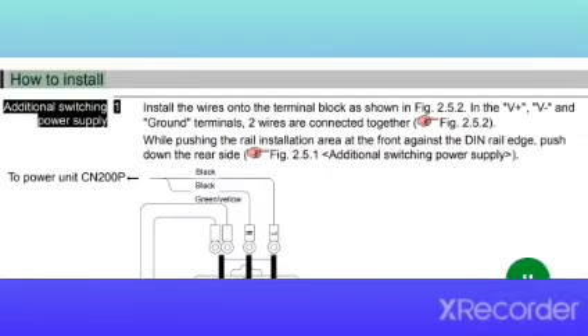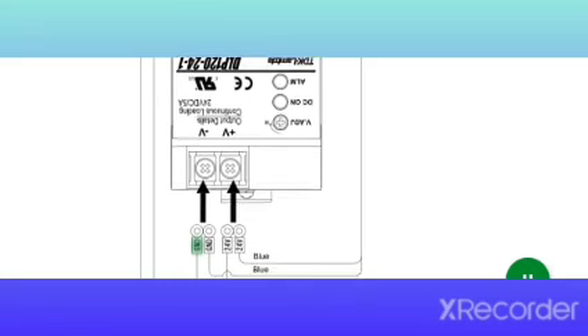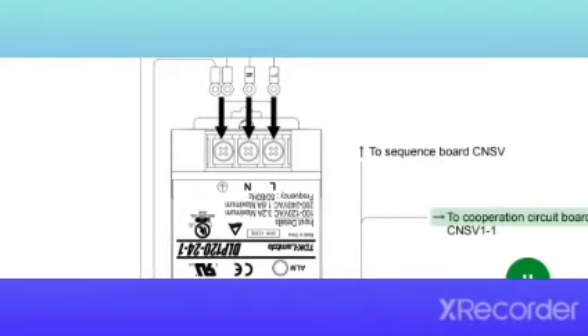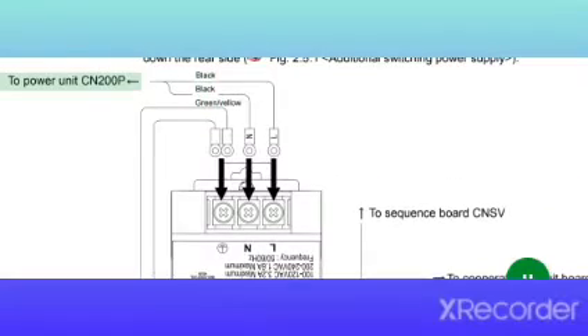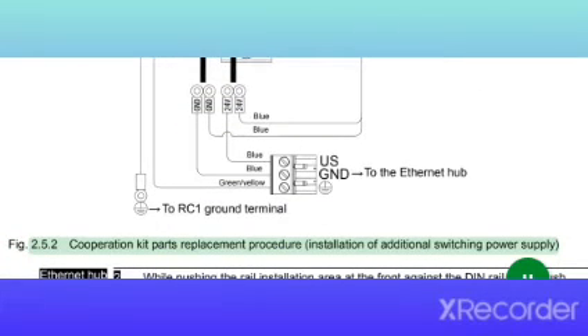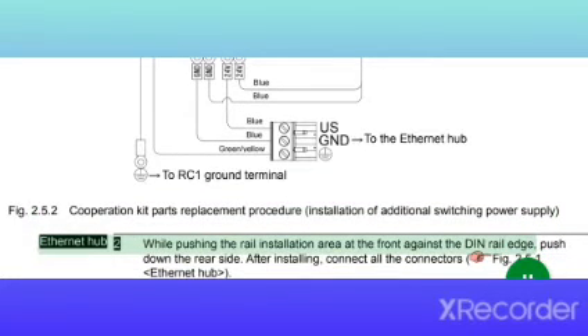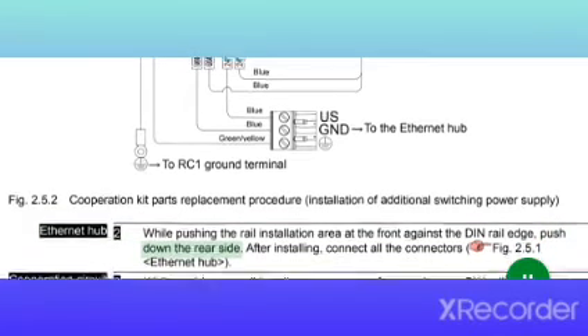2.5 Parts replacement procedures, 2 to 29. How to install. Additional switching power supply: 1. Install the wires onto the terminal block as shown in Fig. 2.5.2. In the plus, minus and ground terminals, 2 wires are connected together. While pushing the rail installation area at the front against the DIN rail edge, push down the rear side. Fig. 2.5.1 Additional switching power supply. Fig. 2.5.2 Installation of additional switching power supply. Ethernet hub: 2. While pushing the rail installation area at the front against the DIN rail edge, push down the rear side.